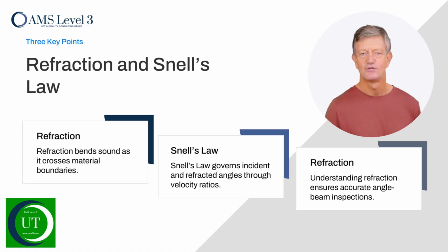Every time your wave crosses from one medium to another, like through a wedge into steel, it bends. That bending follows Snell's law, and it's not optional. Refraction explains why your shear wave enters the part at a predictable angle.